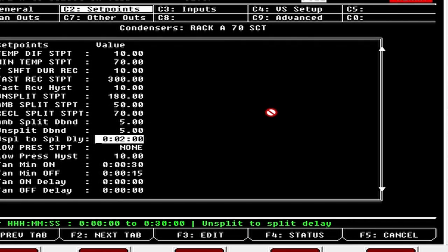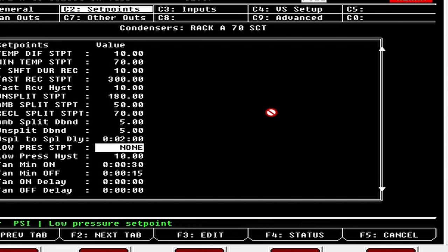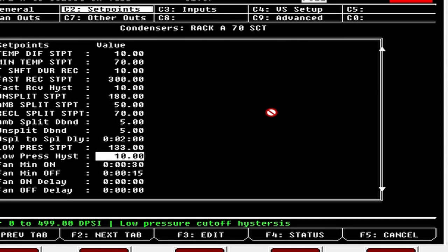On Split to Split Delay: two minutes is fine, I generally don't need to run any lower. Low Pressure Set Point: I set that at generally whatever my hold-back valve setting is going to be — so if I'm trying to maintain 133 pounds as my holdback, I set my low pressure set point to that so it kicks the fans out and they're not fighting the condenser. Low Pressure Hysteresis works the same way — it would have to raise up to 143 before the fans turn back on.